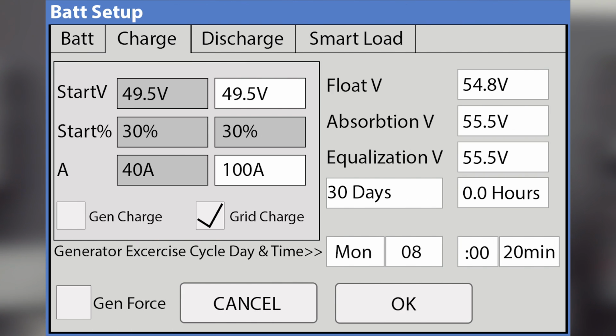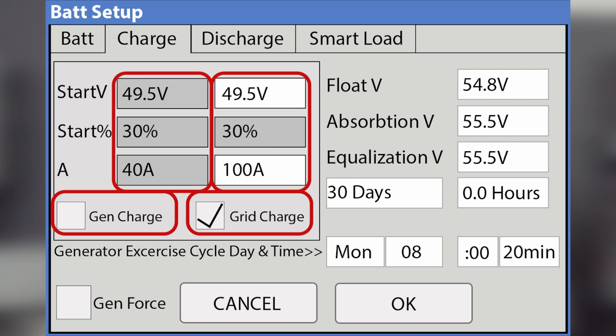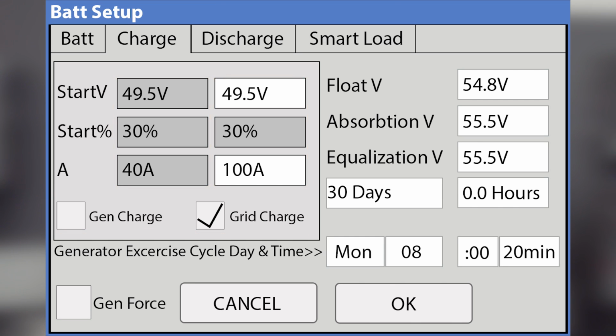Next, we're going to go to the charge tab, one tab over. Here you can control the charge rate from different power sources, so you have your grid charge settings and your gen charge settings. You can change the number of amps coming from each one of those sources. The important thing here is that this is amps at the battery's voltage, not AC amps. So you're going to be able to crank it all the way up to 185 for a 12K, all the way to 275 for a 15K, or whatever model you have.